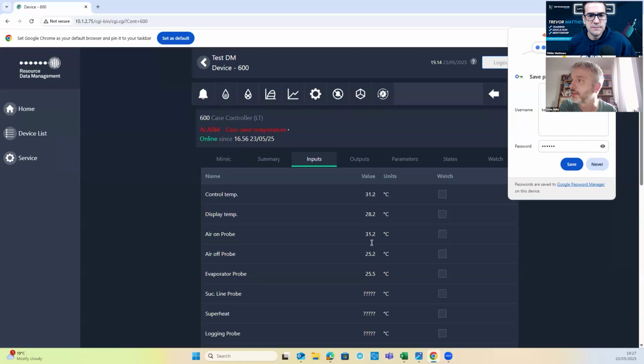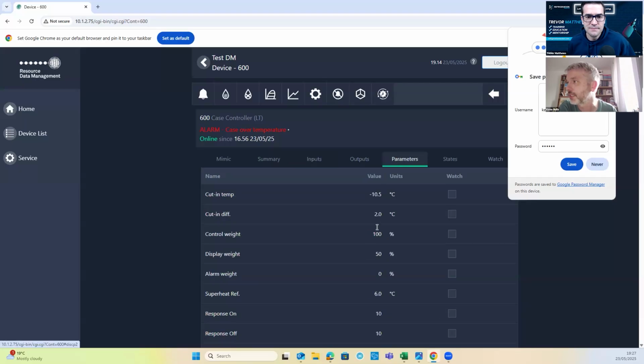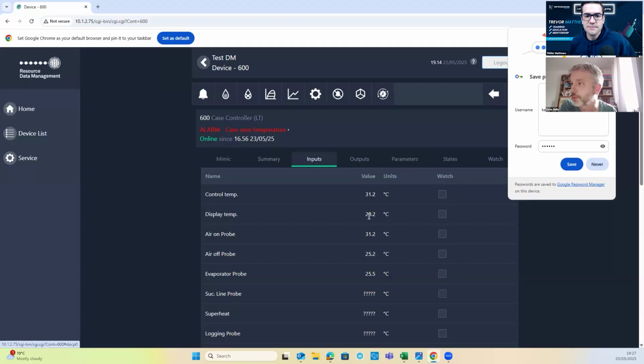So you see, it's reading all of the air on value, whereas before it was reading an average of the two, and that's because I've set it to 100%. The result of the display weight still being on 50 is that it's still showing you the average of the two. Yeah. So that's a good way for, like you said, if the customer's all worried about the produce because it's saying -3, but actually that's the coil temperature. That's a big difference. Yeah, exactly.